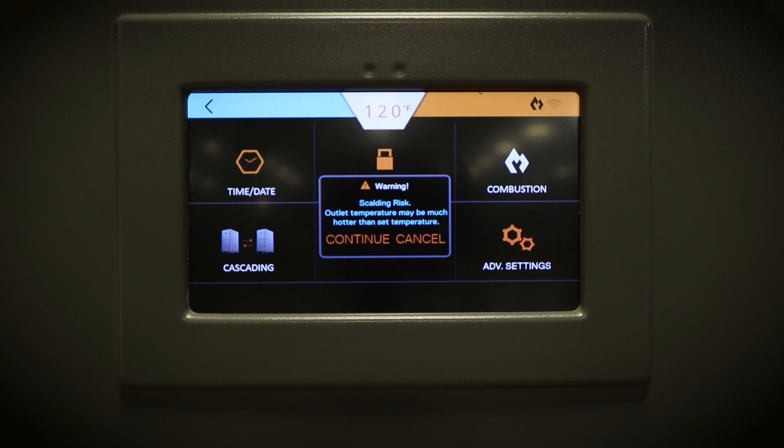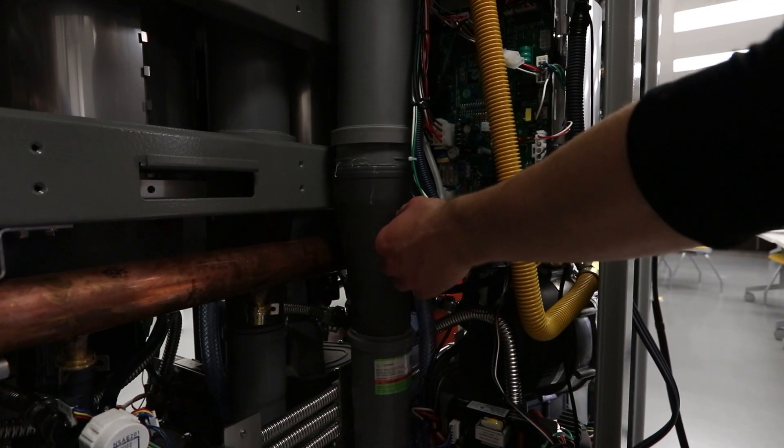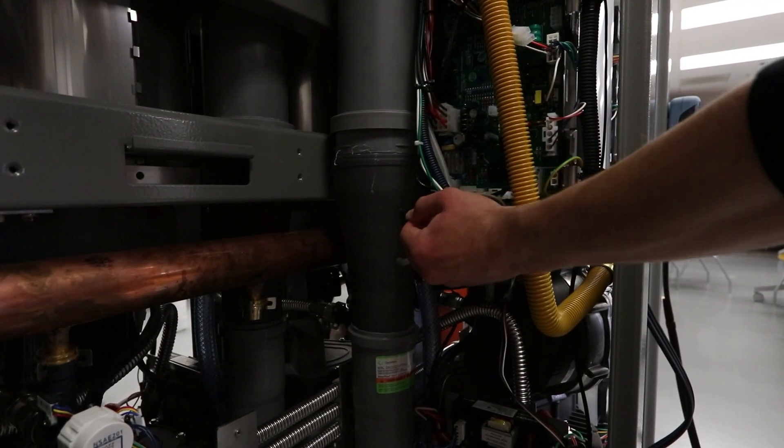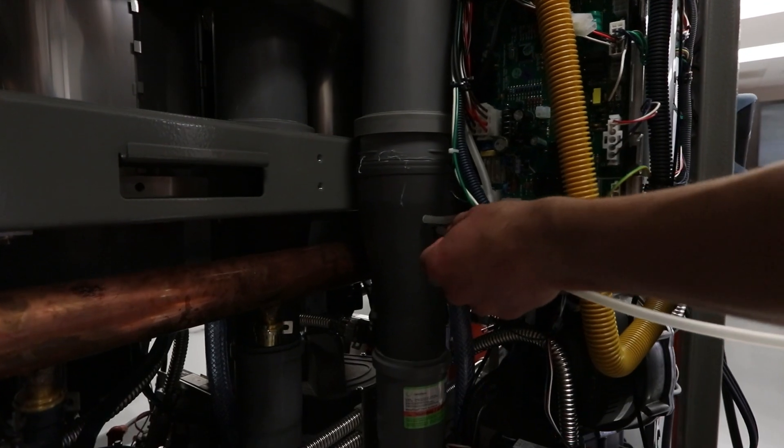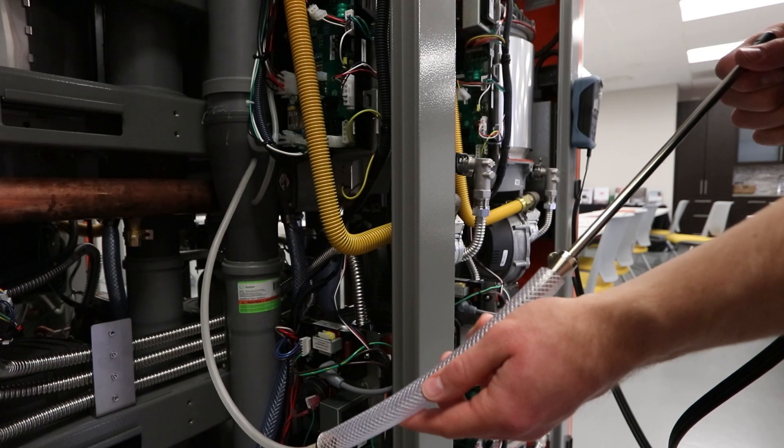Calibrate your combustion analyzer to the fuel type of your unit, either natural gas or propane. Locate the air switch ports on the side cast of the heat exchanger. Remove the top port and place a piece of tubing onto the port. Place the analyzer probe into the opening on the other end of the tubing.